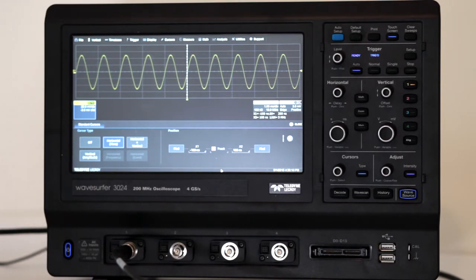The window in the lower left corner corresponds to changes in position of the horizontal lines that measure amplitude. These values are measured in millivolts. The top horizontal line in the display correlates to the third row in the left-hand window and also to the bottom row, labeled delta Y, which means change in millivolts. The bottom horizontal line in the display correlates to the fourth row in the left-hand window and again to delta Y. The vertical lines cross the x-axis, bracketing portions of the time base so that it can be measured.